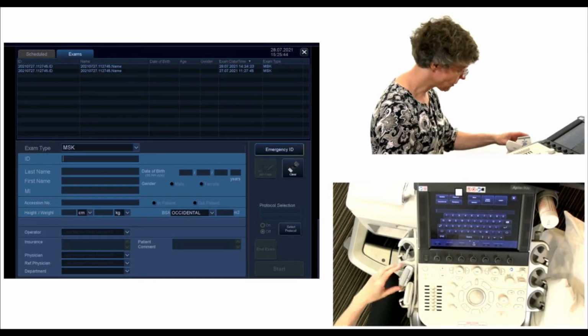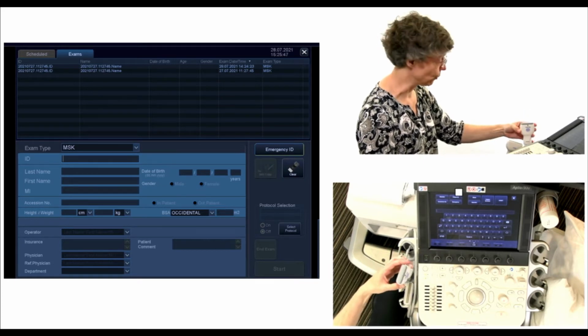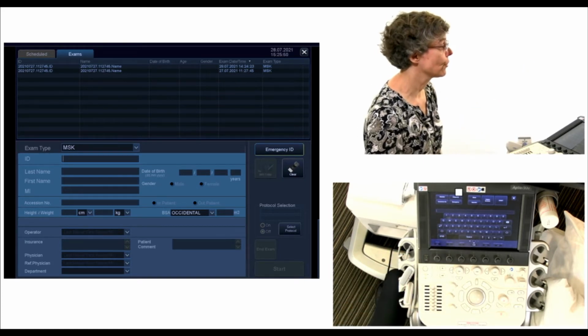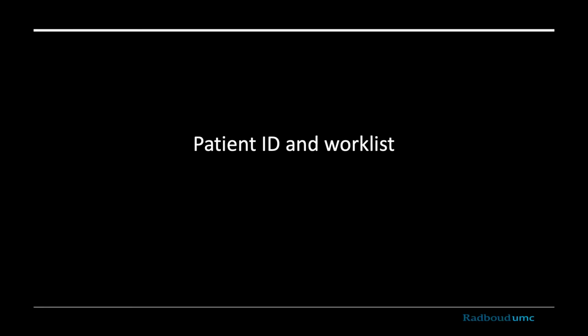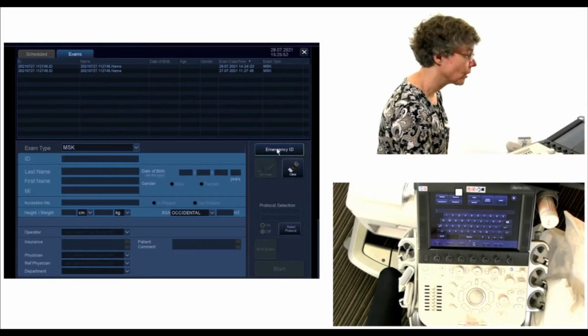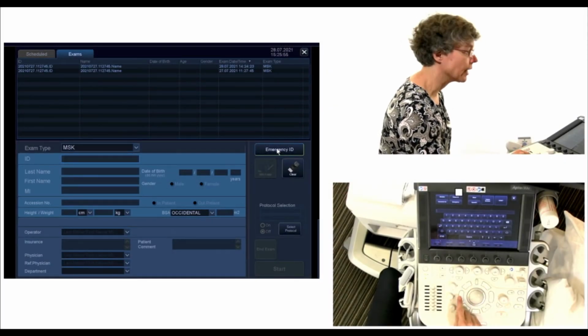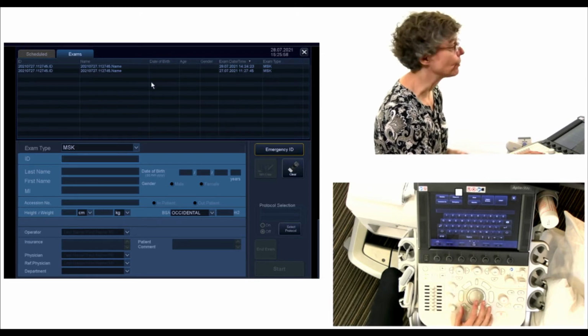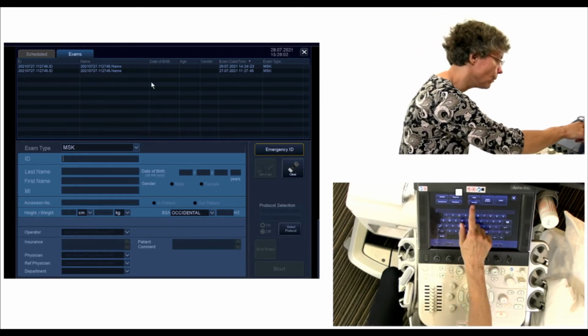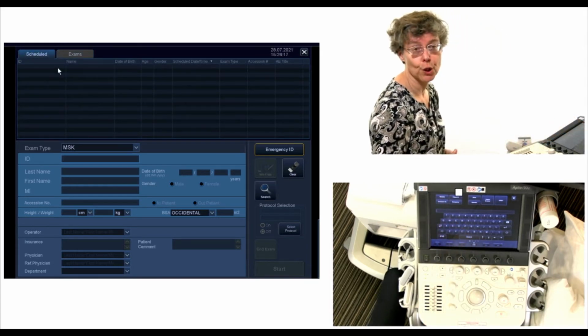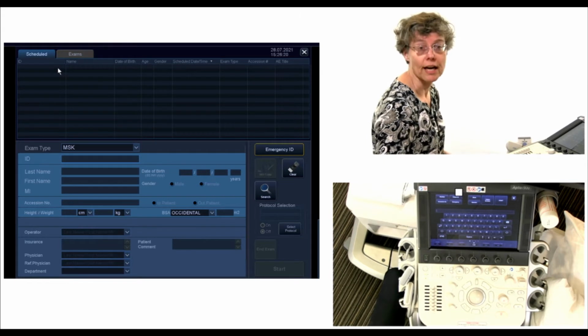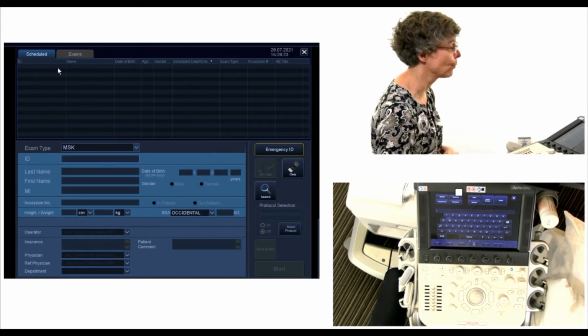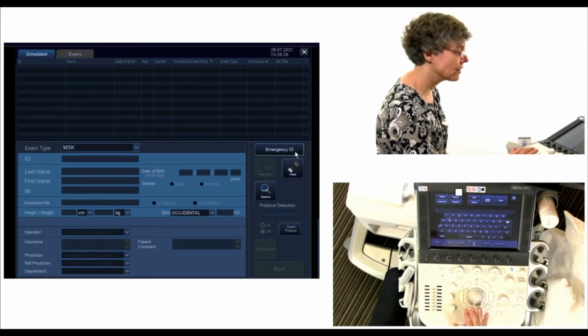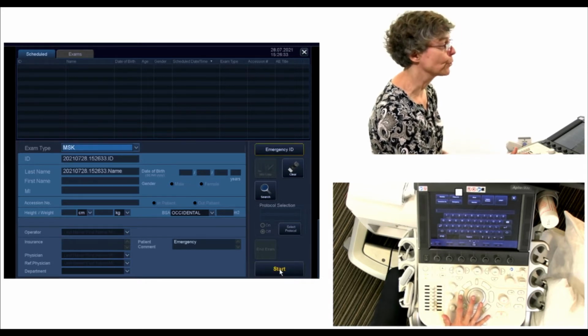Okay, so in this case, we're going to start out with the nice high-frequency linear probe in a second. You can see the machine has already turned itself on. We're going to use an emergency ID in this case because we're not entering any patient details, but if there were patients, you could find them in what's called the work list. But if you have an attachment to your hospital or practice system, the patient that will be scheduled could be shown here, and you could select the patient and import all the information you have there. So in this case, we don't have a patient, so we're going to start out with what's called an emergency ID, some temporary ID, so you can find the study details back. Now, it fills this out for us.